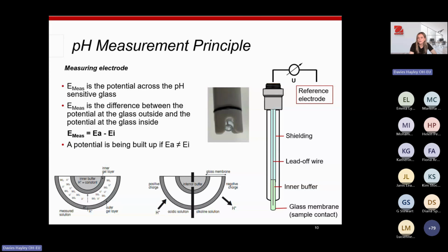The measuring electrode, inside, you have the lead-off wire, which is immersed in the inner buffer. And this lead-off wire carries the electrical signal, or the voltage, to the meter. You've got the glass membrane, or the tip. We'll call it the glass membrane, the tip, either or really. The tip is made of specialized pH sensitive glass. When it's dipped in a liquid, a thin hydrated gel layer forms on the outside, and hydrogen ions in your sample react with this layer, creating the voltage essentially that the meter reads.